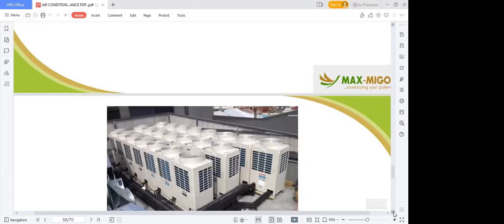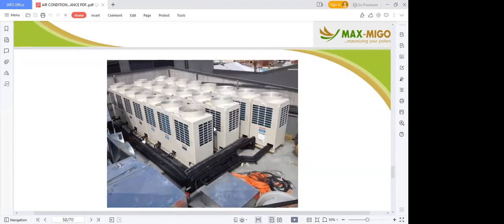Then this is a VRF system. This one, you can actually install like this because they have an up discharge of cooling. And you see how their copper pipes are well arranged. Please don't forget, when you do your installation like this, let your technician do tagging so that they will know the copper pipe that is associated with the outdoor unit.